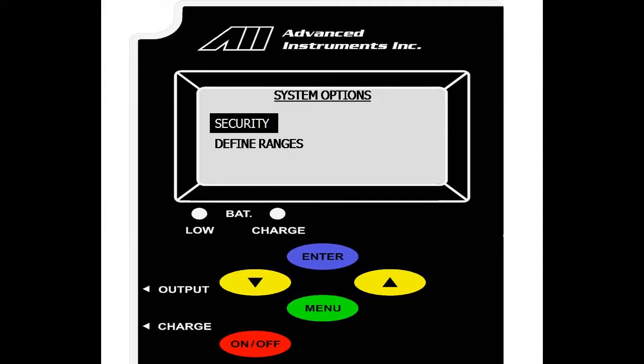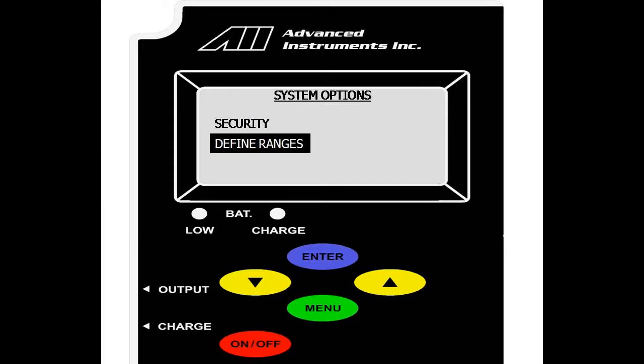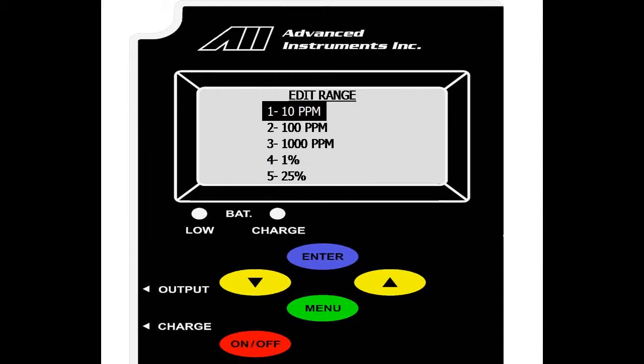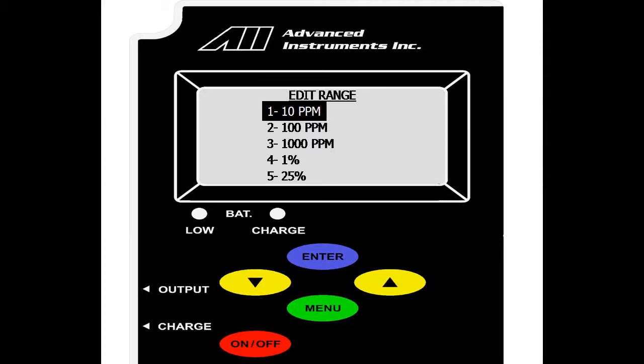We are back to the system options menu and we will go over define ranges. We have edit ranges, default range, default range delay and out of range. Under the edit range options, we have our five standard ranges which can be user configurable. Be sure to note that the ranges cannot be adjusted below the minimum factory default range nor above the maximum factory default range. Nor can the ranges overlap as well.